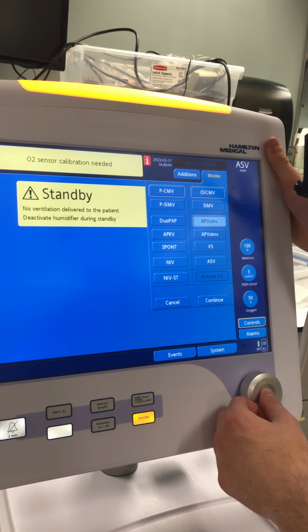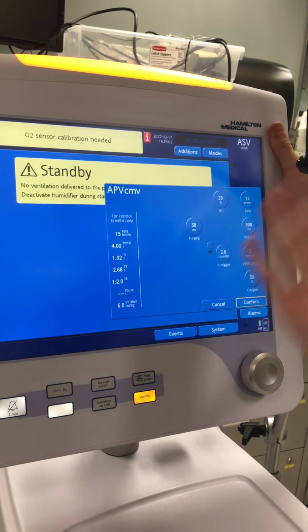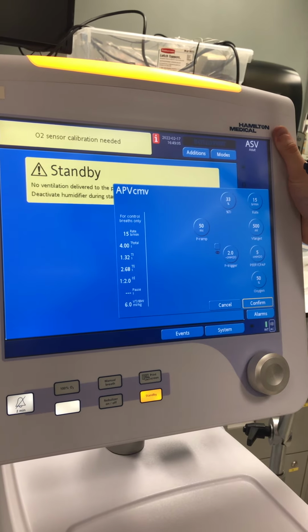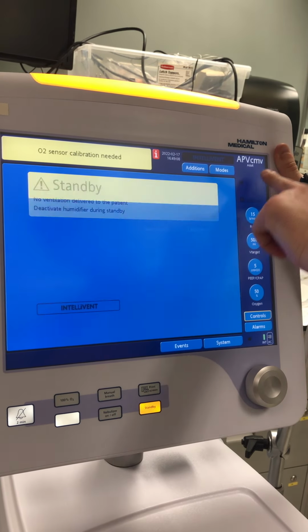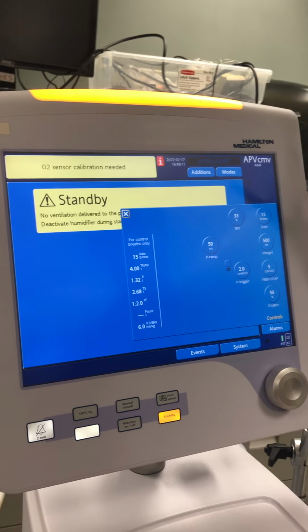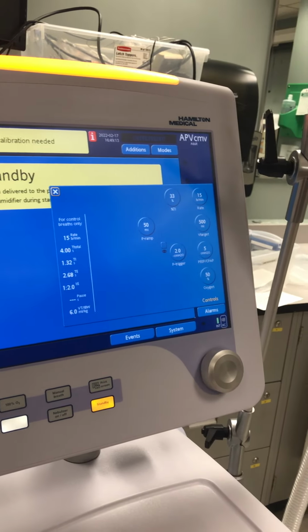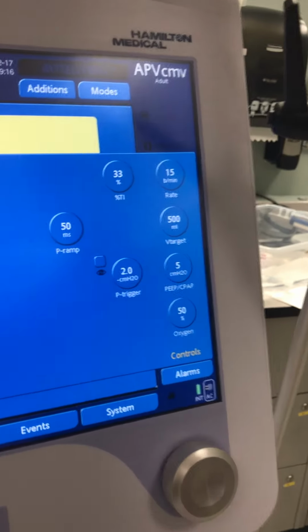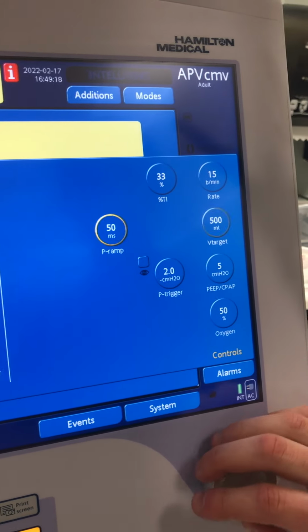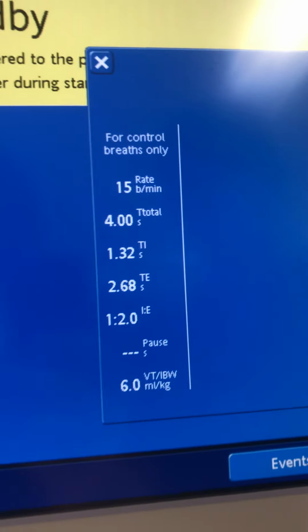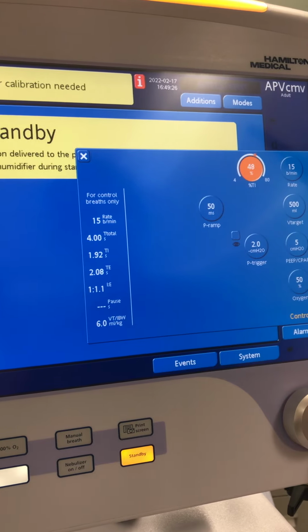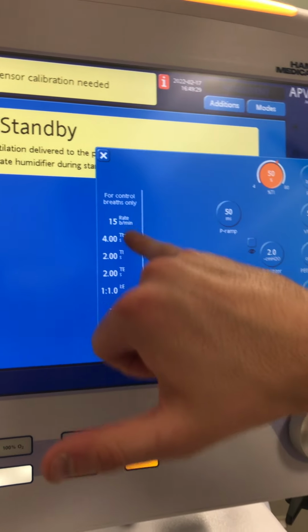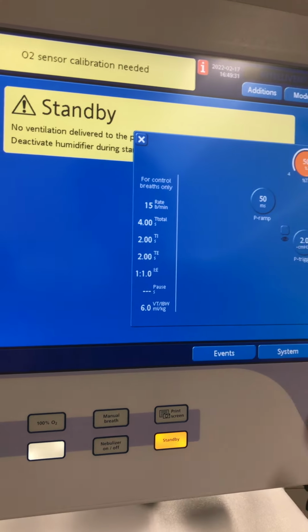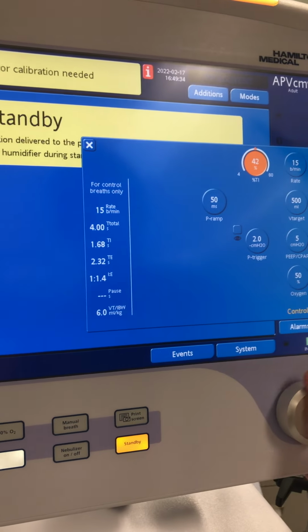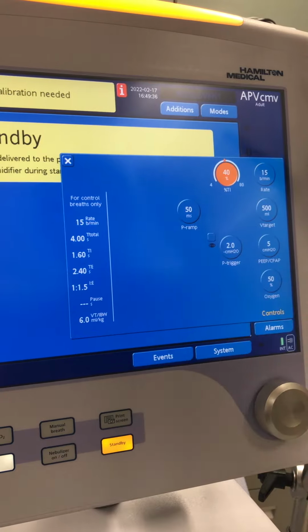You want to go to PRVC, you want to press continue. Important, even if you change nothing, you want to make sure you press confirm. Otherwise, you'll notice the mode will not change. So you press confirm, it has now changed. Controls, change whenever you need to change. One keynote about this ventilator, it says TI%. You cannot change TI as a number directly. You have to change the percentage of the total cycle time. So if I change this to 50%, you'll notice that 50% of it is breathing in, 50% is breathing out. So TI percent of total cycle time, that is breathing in.